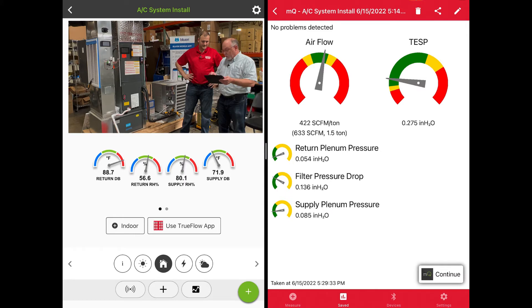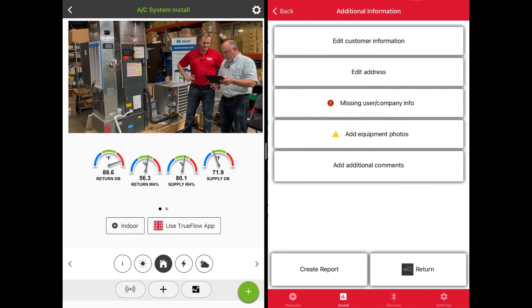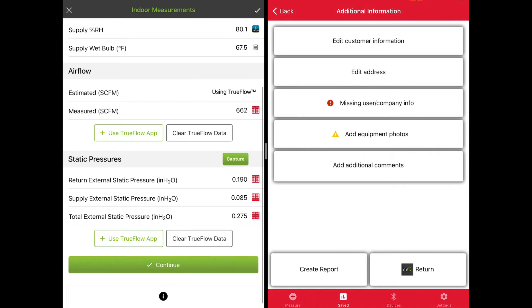Down at the bottom here we can review our test. Our airflow is in the right range, static pressure looks good. We've got our three pressures: return, filter pressure drop, and supply plenum pressure. We hit Continue in MeasureQuick, then hit MeasureQuick Return. If we go into the indoor readings, you will see that we have our measured CFM, our return static, supply static, and total external static from the TrueFlow Grid.